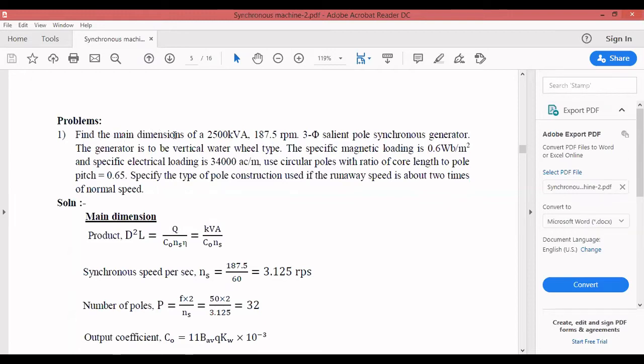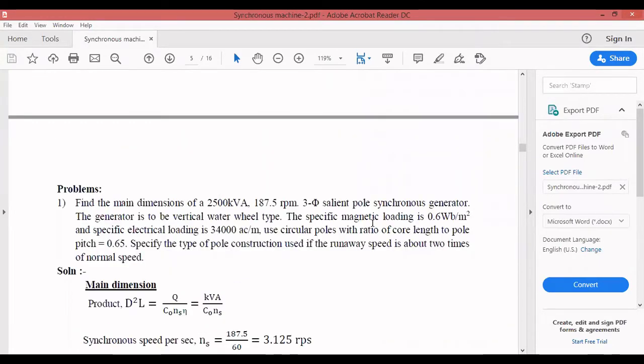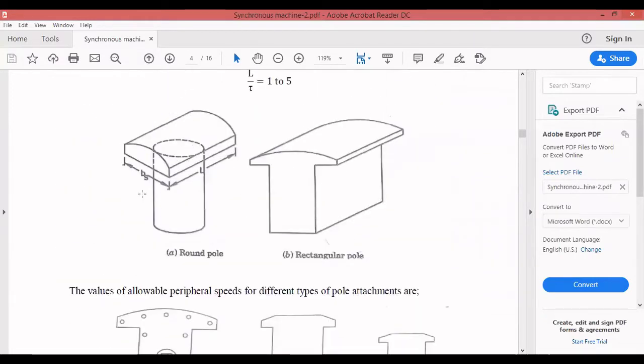Let us go to our first problem: find the main dimensions of a 2500 kVA, 187.5 RPM, three-phase salient pole synchronous generator. The generator is to be a vertical water wheel type — definitely a hydro turbine. The specific magnetic loading is 0.6 Wb/m² and specific electrical loading is 34,000 ampere conductors per meter. Use circular poles, with the ratio of core length to pole pitch equal to 0.65.